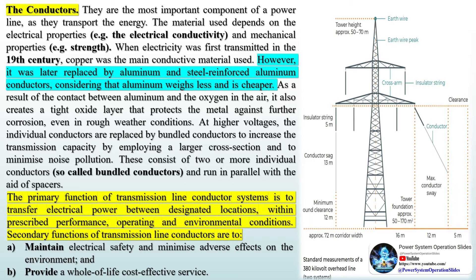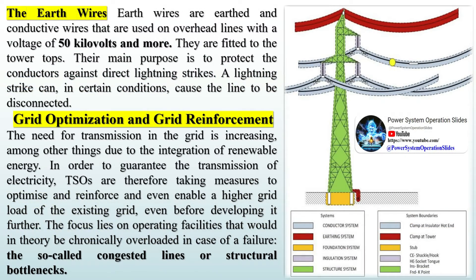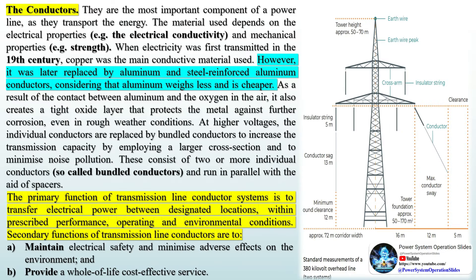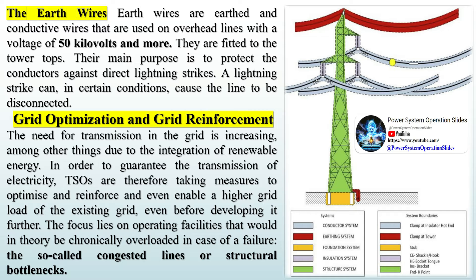The primary function of transmission line conductor systems is to transfer electrical power between designated locations, within prescribed performance, operating, and environmental conditions. Secondary functions of transmission line conductors are to maintain electrical safety, minimize adverse effects on the environment, and provide a whole-of-life cost-effective service. The earth wires are earthed conductive wires used on overhead lines with a voltage of 50 kV and more. They are fitted to the tower tops, and their main purpose is to protect the conductors against direct lightning strikes.